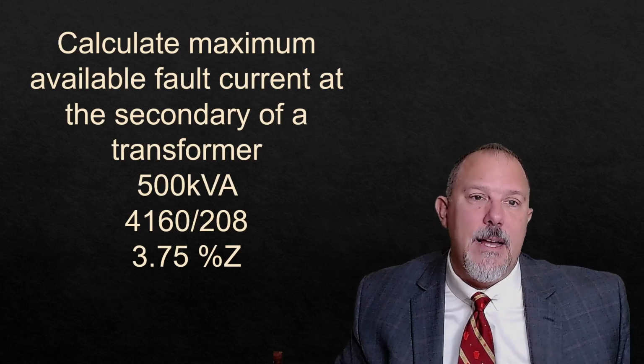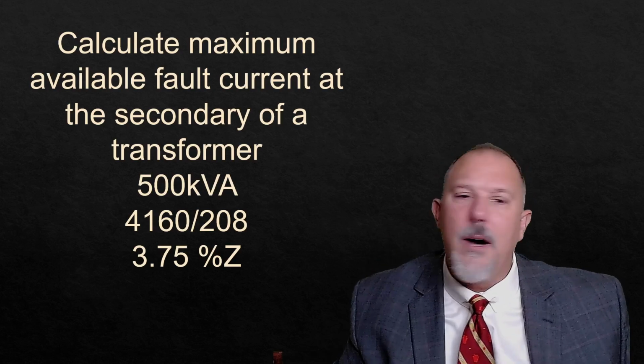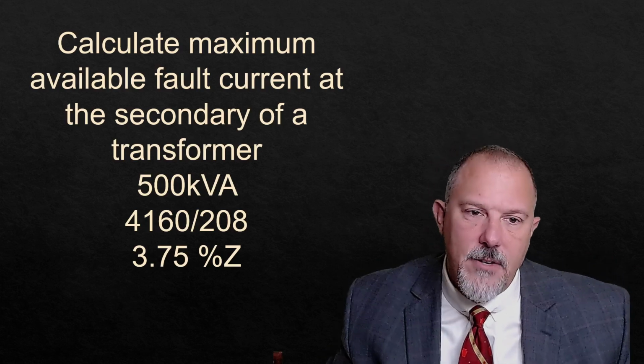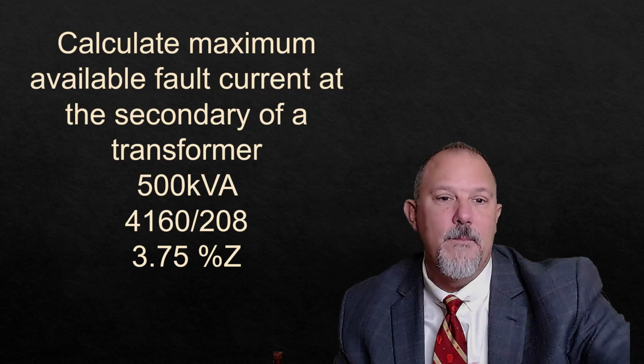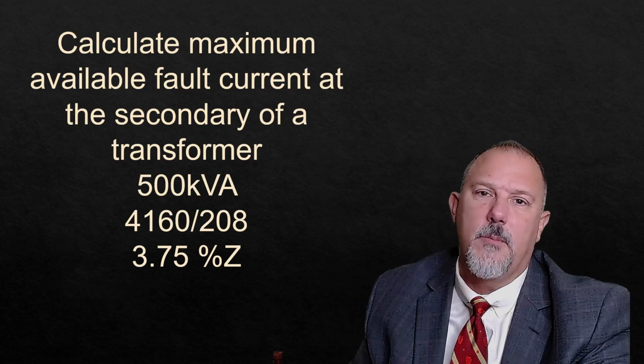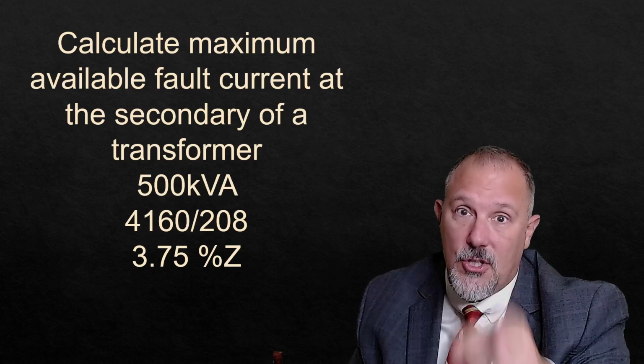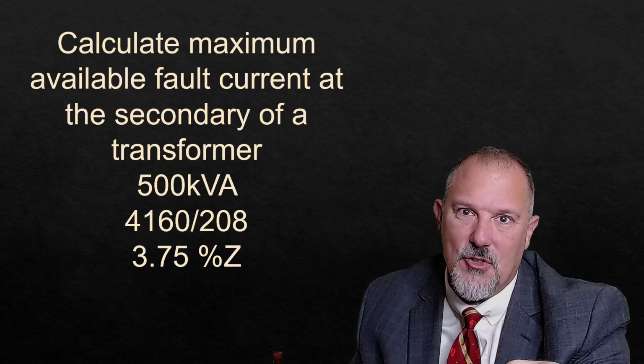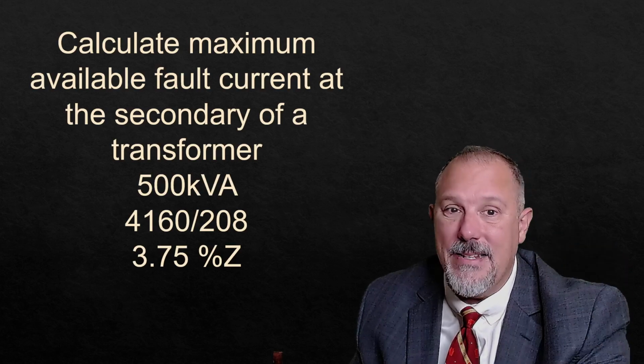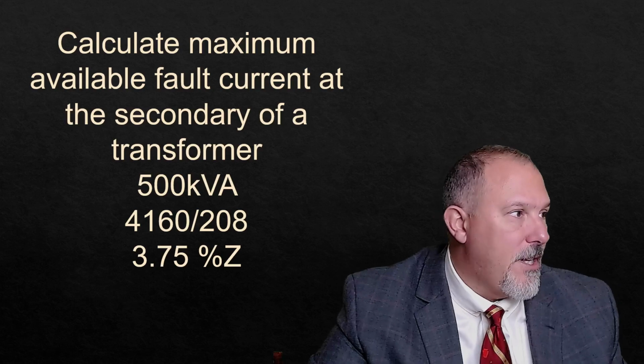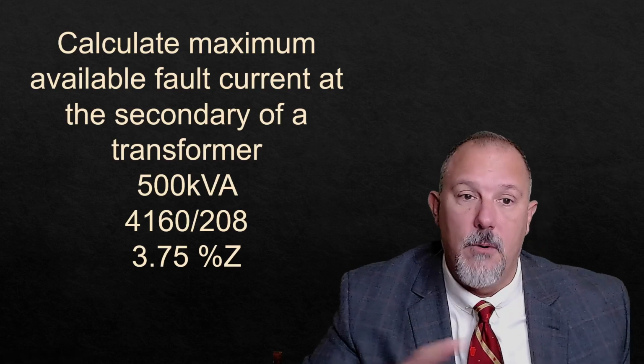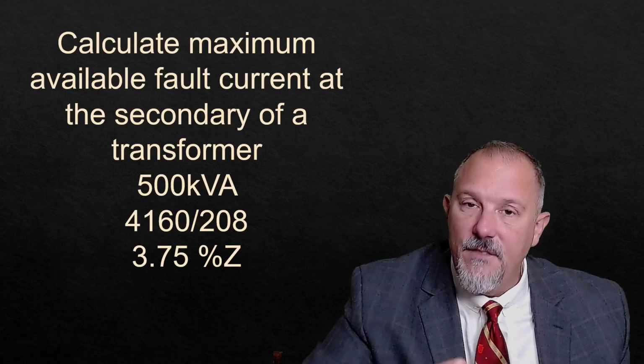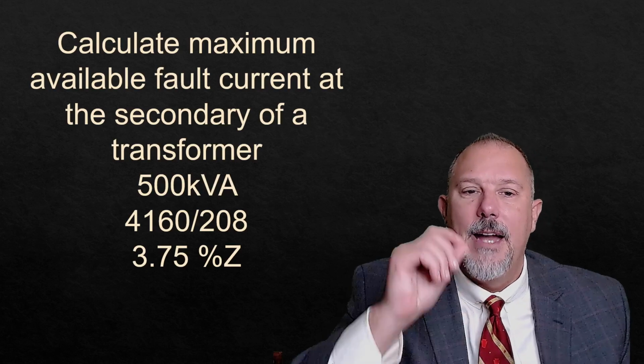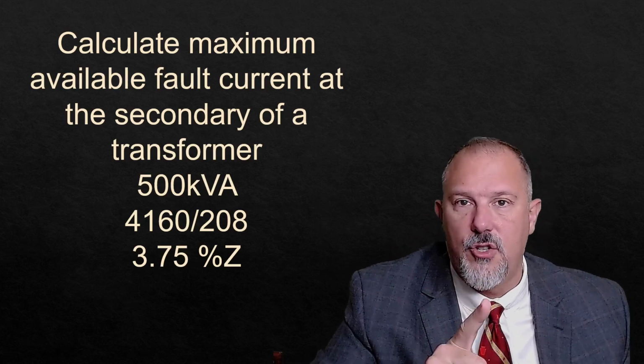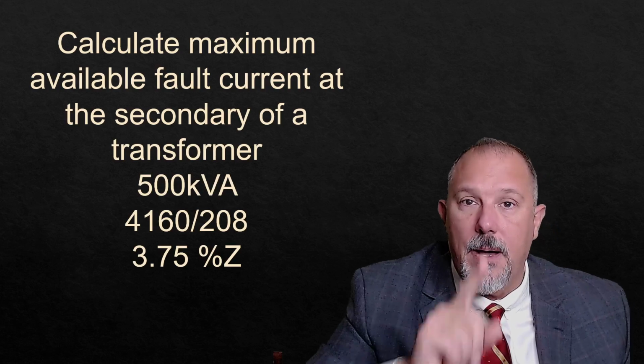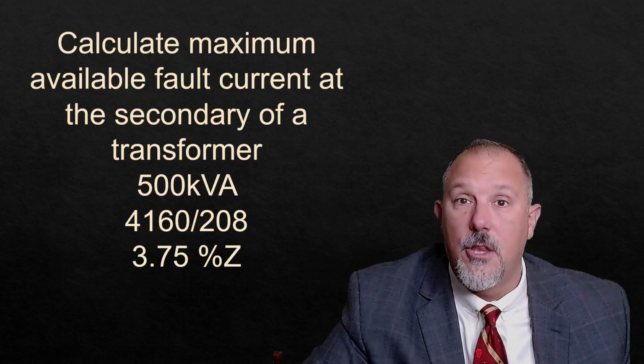All of that information. Let's do an example of maximum fault current that you could possibly see on the secondary of a 500 kVA transformer, 4160 to 208. If I'm looking at the secondary, I don't care if it's 4160 on a primary, it could be 480 to 208. It's the 208 number I'm interested in, the kVA that I'm interested in, and the percent impedance. Now, the equation to calculate fault current is very simple. We call this the infinite bus calculation on the secondary of a transformer. I take the full load amps on the secondary of this transformer, multiply it by 100, and then divide that by the percent impedance, the 3.75.